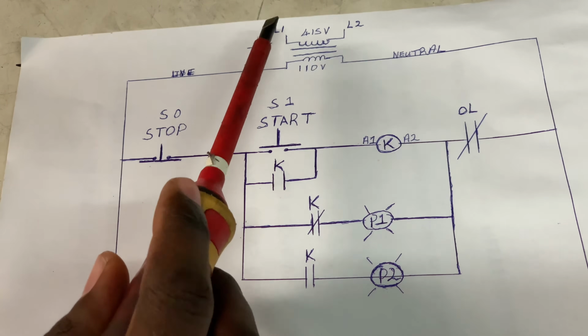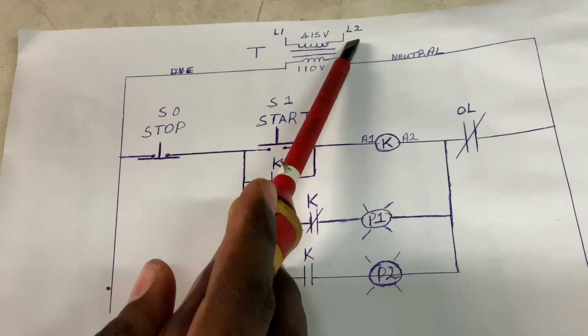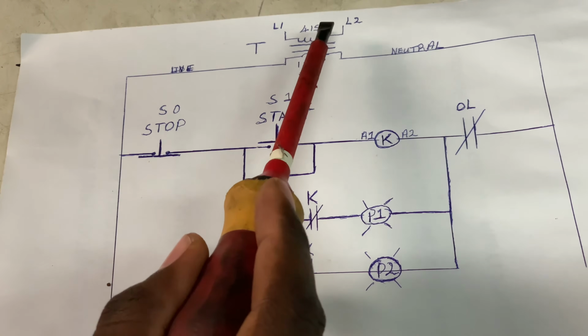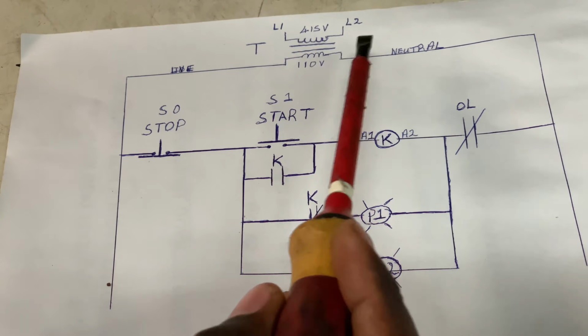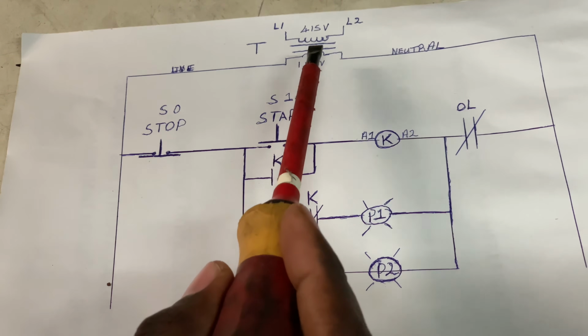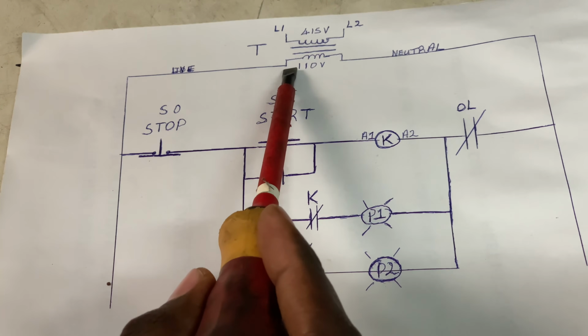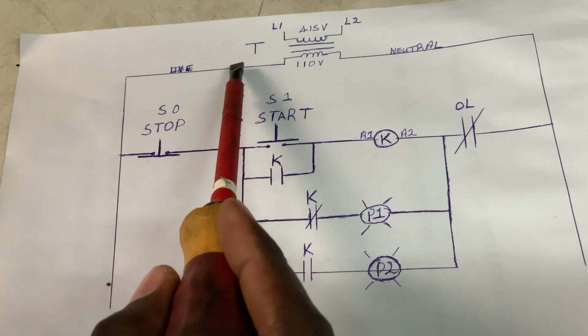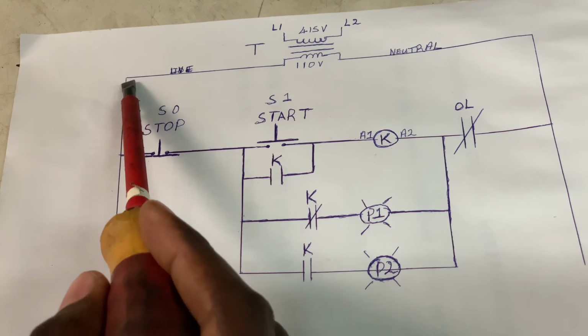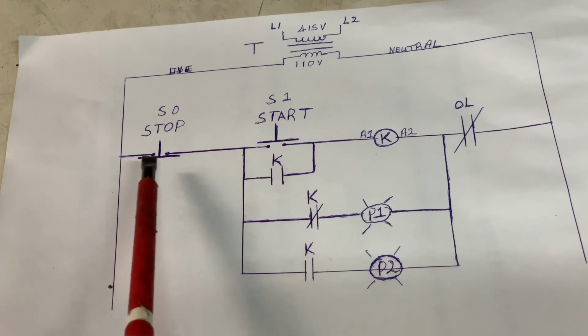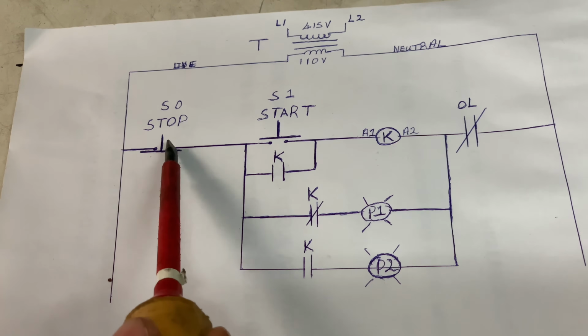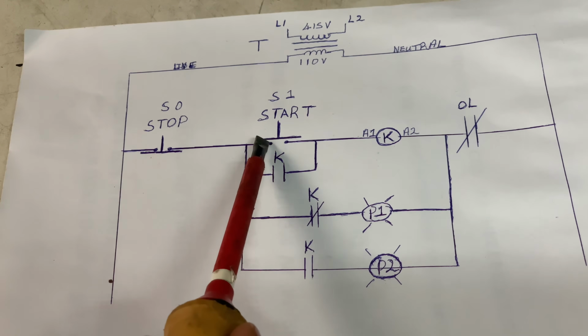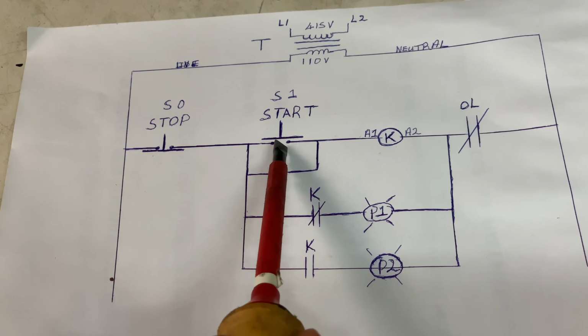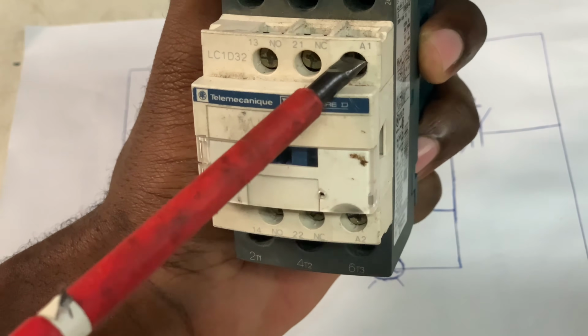Alright, so here what happened is I took a line from line 1 and line 2 and connected to the primary side of the transformer. Then the transformer stepped down that voltage to 110. Right? So from the secondary side of the transformer now, I took the 110 line and I connected to the stop push button. So from the other side of the stop push button now, it goes to the start push button. Then from the start to A1, which is here on the contactor.